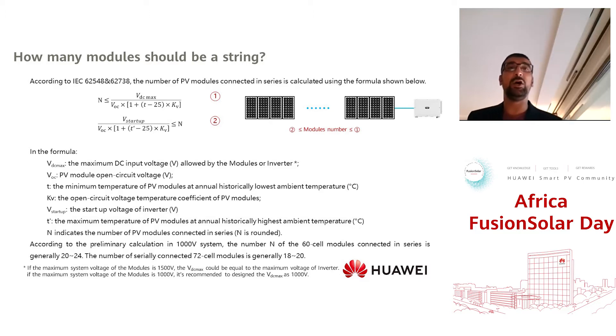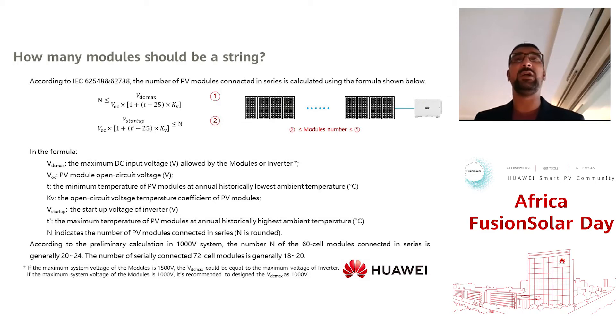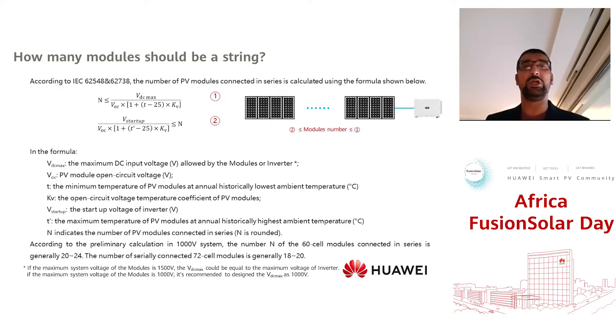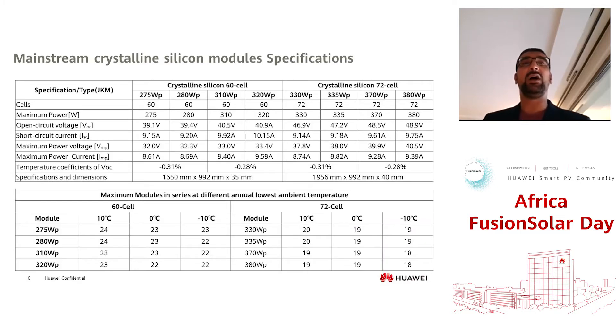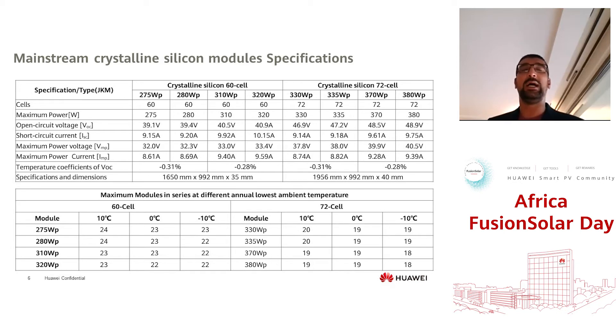Depending on the geographical location, the startup voltage and the operating voltage of the inverter — specifically the MPPT window — you need to ensure that the string voltage is suitable. In areas where the temperature can get quite low, you do need to consider that minimum temperature value in the equation. The calculation is shown on screen, and depending on whether you're considering a 60-cell or 72-cell PV module, there are several factors to extract from the module documentation.